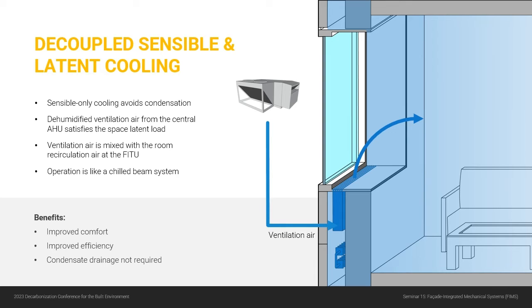So for those of you who are familiar with chilled beam systems, it essentially operates the same exact way. You can even think of the FITU as like a chilled beam. The only difference is that, at least for the way we're designing it, we're using a fan instead of induction nozzles. But other than that, this is essentially exactly like a chilled beam system.